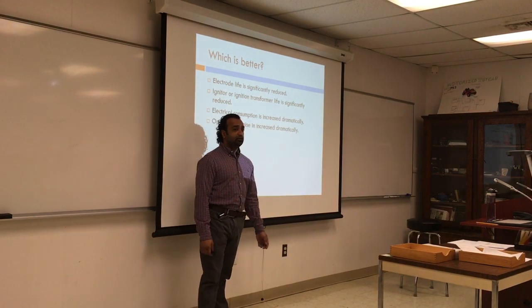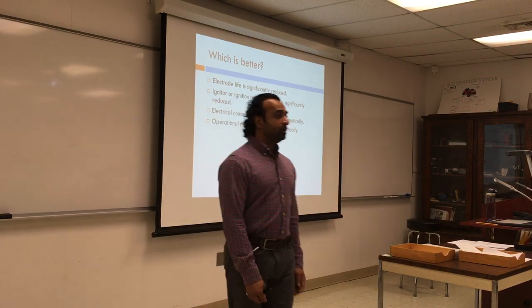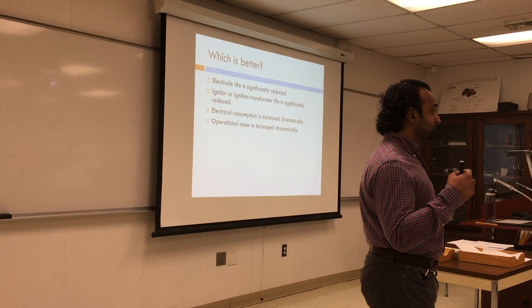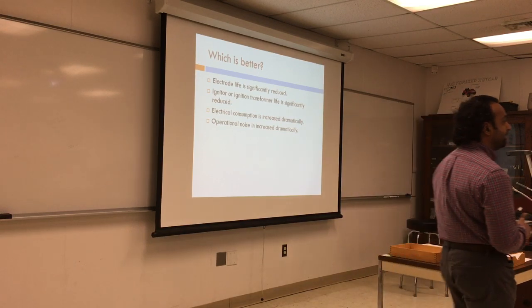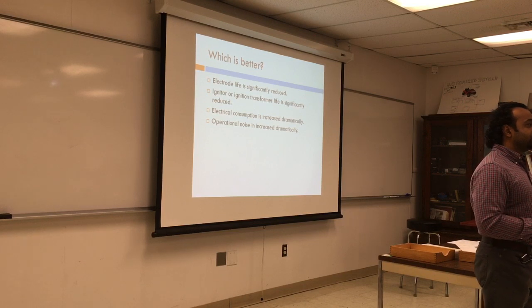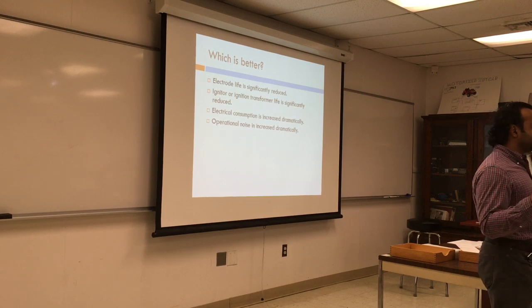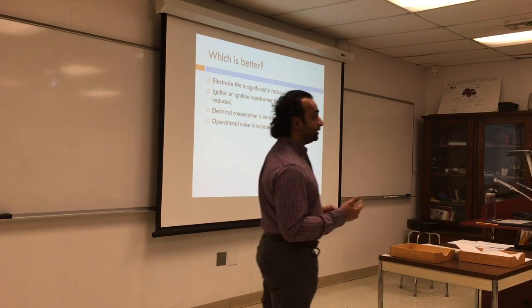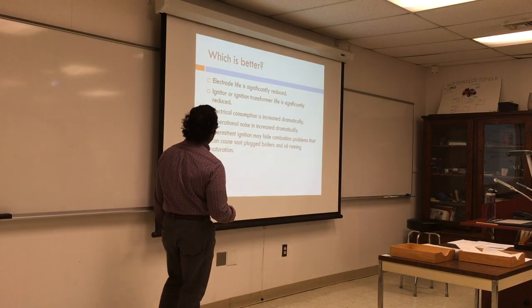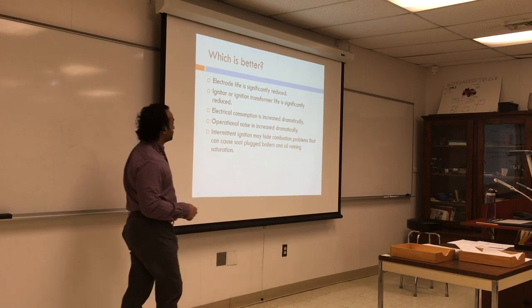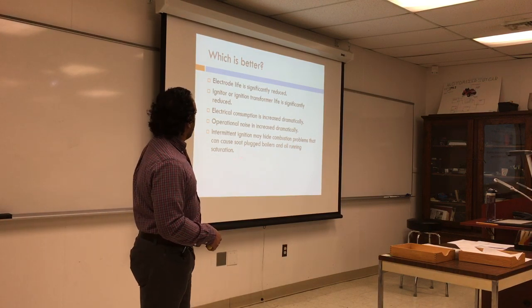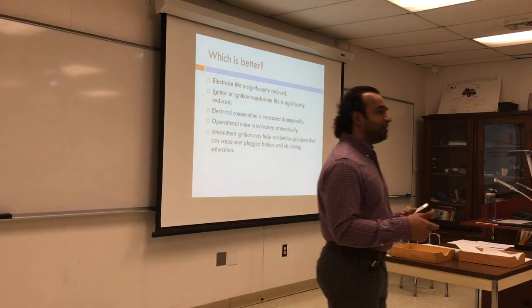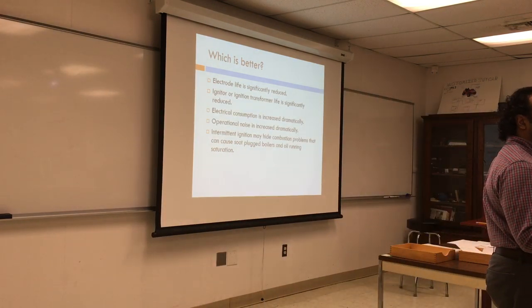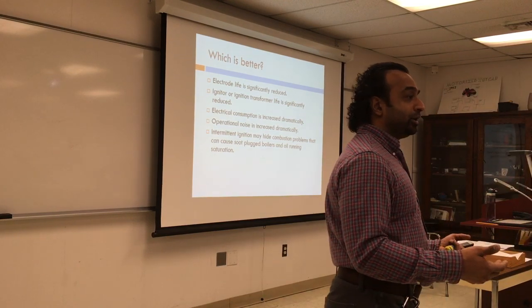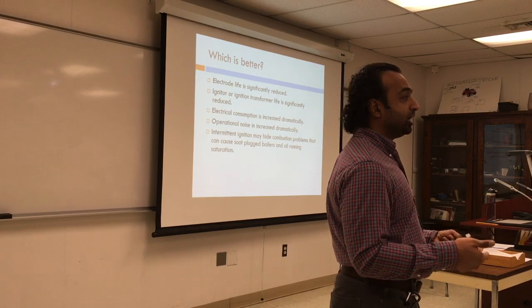Operational noise is increased dramatically if you have interrupted ignition. You can hear the buzzing. If you have a gas furnace, once you turn it on, you'll hear the ignition coming on and off until the flame comes out and then the ignition is shut off. So the buzzing is really loud, so it will produce noise. Intermittent ignition may hide combustion problems that can cause soot that plugs the boiler and oil saturation. So if you have constant ignition, whether you're running lean or rich or too much oil coming in, it's always going to burn because you have a source of ignition the entire time.